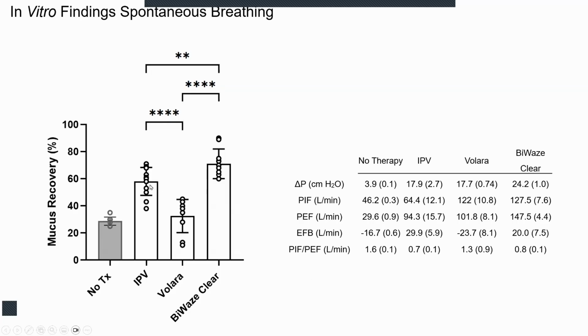With the IPV, we see quite a bit of the secretions eliminated from the airway and going into the trap. With the Volara, we don't see as much, and it's not really that different from just normal spontaneous breathing. With the BiWaze Clear, we see somewhere between 60 and 80% of the secretions being removed. Each of these devices does it a little differently. The BiWaze Clear has a different I to E ratio for its oscillation than the IPV. We know that the IPV has a shorter inspiratory time and a longer expiratory time, and that really helps facilitate secretion movement, even with lower delta pressures and lower flows.